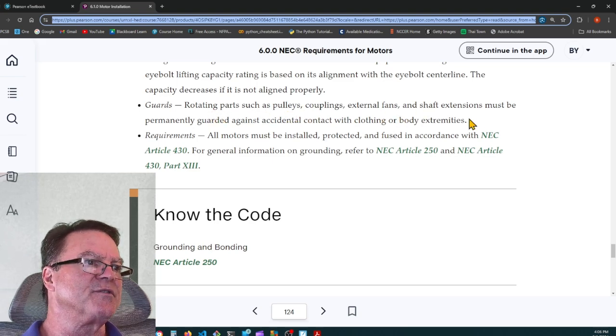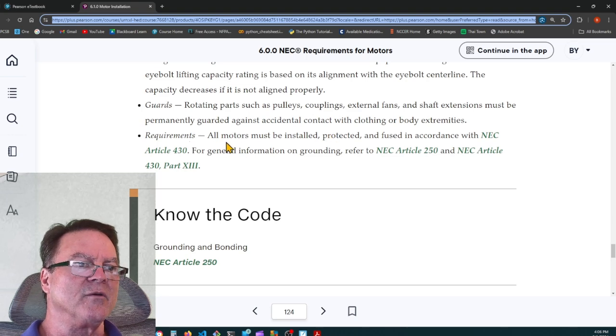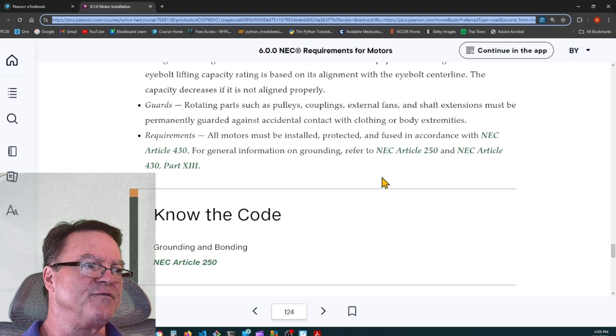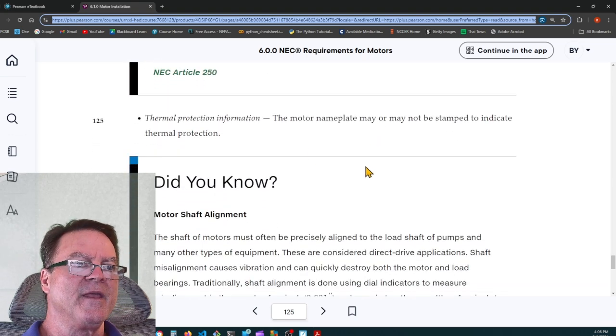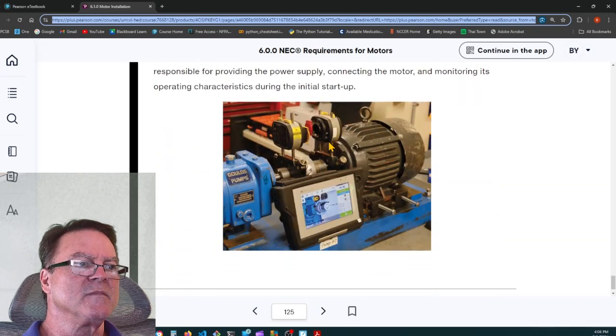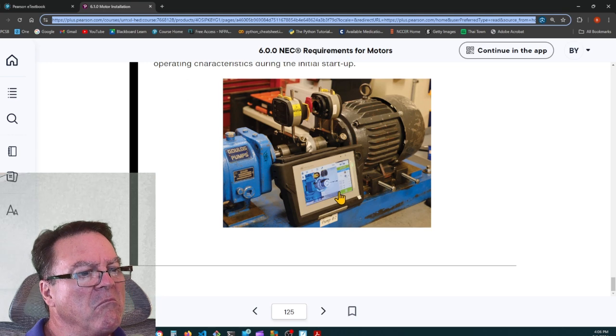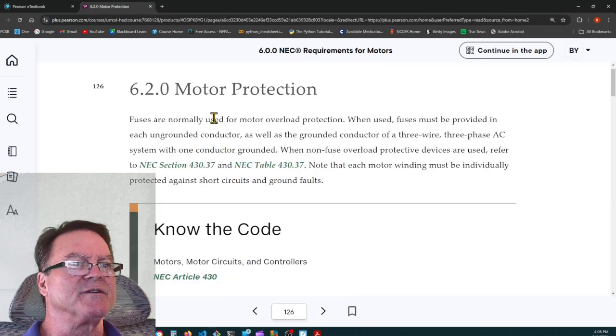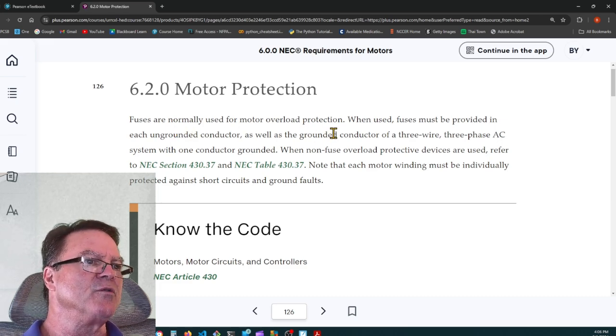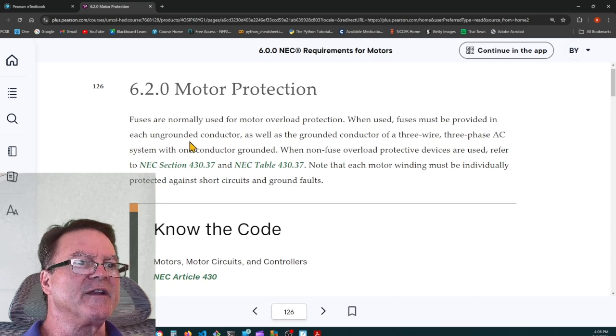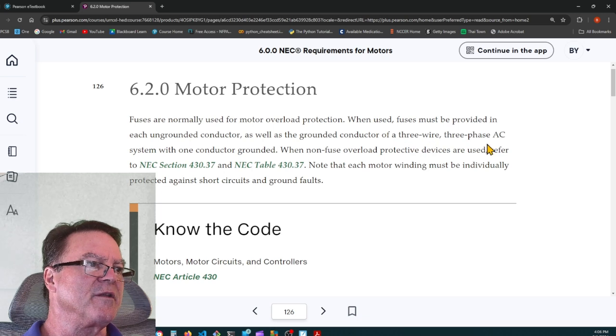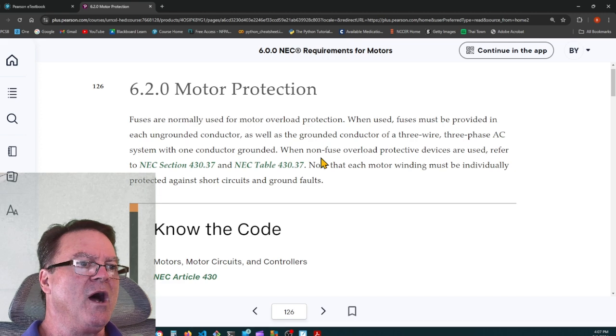Guards: rotating parts such as pulleys, couplings, external fans, and shaft extensions must be permanently guarded. Requirements: all motors must be installed, protected, and fused in accordance with NEC Article 430. For general information on grounding, refer to Article 250 and Article 430, Part 13. Thermal protection information. The motor nameplate may or may not be stamped to indicate thermal protection. All right. Motor protection. Fuses are normally used with motor overload protection. When used, fuses must be provided in each ungrounded conductor as well as the grounded conductor for a 3-wire, 3-phase AC system with one conductor grounded. When non-fuse overload protective devices are used, refer to NEC section 430.37 and table 430.37.